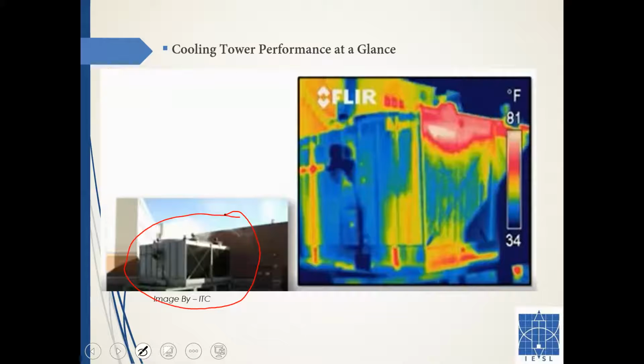You can see the solar loading here, the sunlight. The sunlight is not good for our surveys, it always masks off the important information you need to find. In this instance, there's a solar shading right here, and in the thermal imaging you can see the exact pattern on the cooling tower. That's the effect of the solar loading. You cannot do a survey with the sun on.